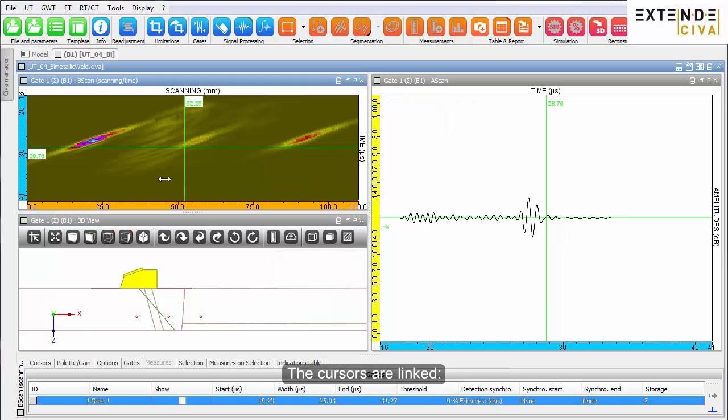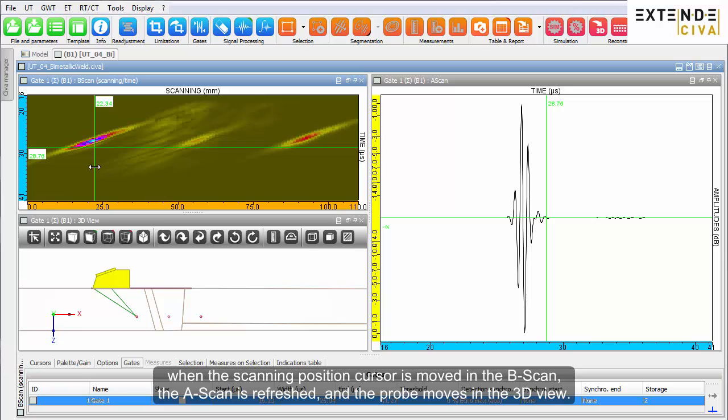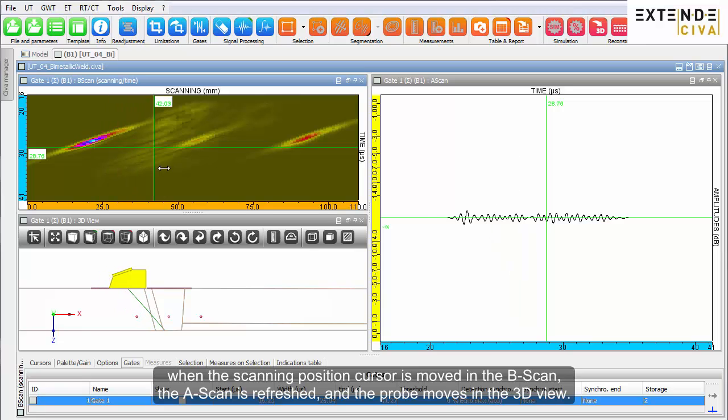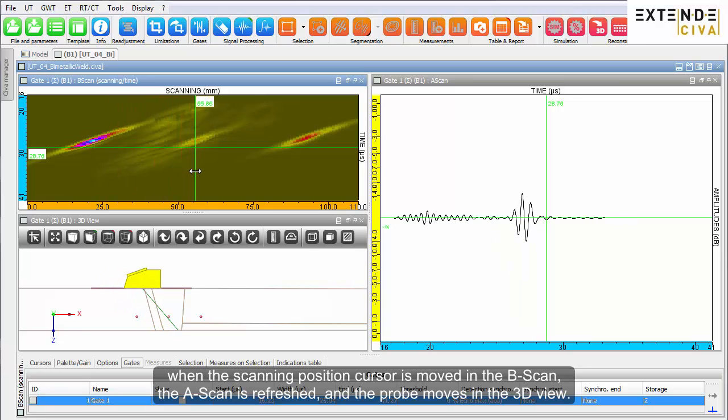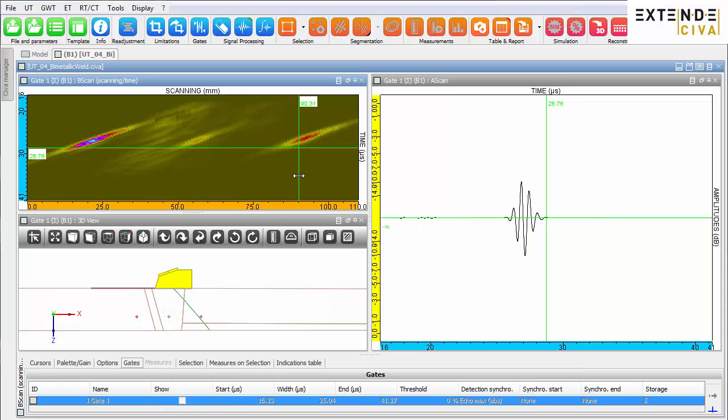The cursors are linked. When the scanning position cursor is moved in the B scan, the A scan is refreshed and the probe moves in the 3D view.